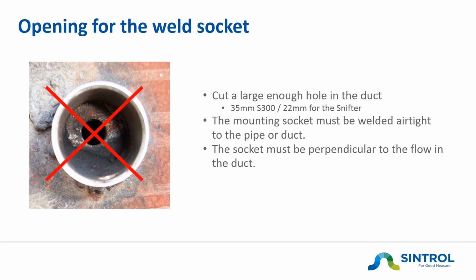Then the weld socket. Please cut a large enough hole into the duct. Not like here. The hole should be completely open all to the diameter of the socket. That would mean you cut about a 35mm hole for the S300 socket and a 22mm hole for the Snifter socket. After that, please weld an airtight welding all around the socket and make sure that it is perpendicular to the flow in the duct.